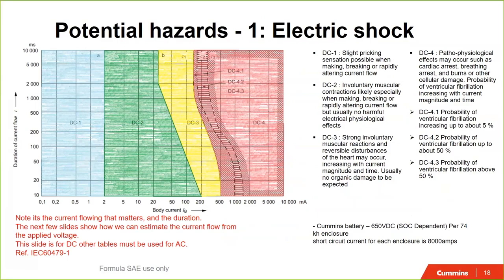If we look at a Cummins battery at 650 volts DC, depending on its state of charge, it has a short circuit capability of 8,000 amps. On the graph on the screen, we're at 10 amps on the far side. If we take that out to 8,000 amps, we're in another building. You really do need to be careful with high voltage battery systems, particularly next year when you go up to doubling in size.